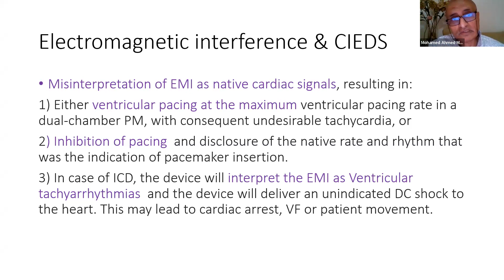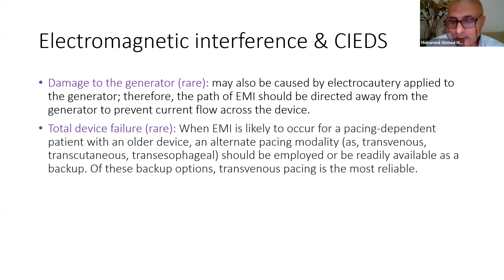Another rare effect of these machines on the cardiac devices: if the surgeon applies the cautery machine directly on the generator of the device, it may cause direct damage to the device, which is a rare complication. Sometimes a strong electromagnetic field near the cardiac device will produce total device failure. The device will not sense, will not pace, and will not deliver any defibrillation shock to the heart. Another rare complication of electromagnetic interference is activation of what is called power on reset, something that resembles what happens in our mobile phone when you reset to the factory setting. So the pacemaker will be reset to the manufacturer setting.